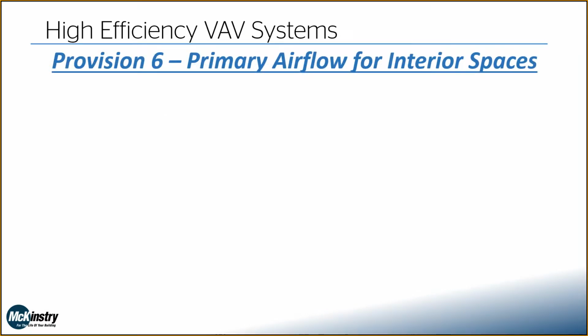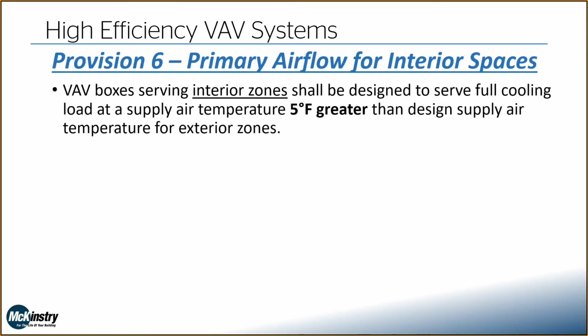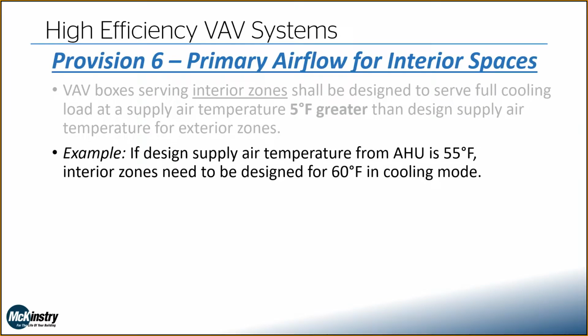So, primary airflow for interior spaces. If you have a VAV box serving an interior zone, meaning any zone that does not have an exterior wall exposure, you have to size that box to serve the full cooling load at a supply air temperature 5 degrees greater than the design supply air temperature for exterior zones. So as an example, if we design our air handler to provide 55 degree air on a design day, on our interior zones, we need to assume that those are actually getting 60 degree air.